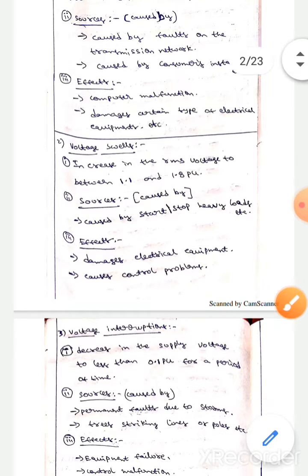The next one is voltage swells. It is an increase in the RMS voltage to between 1.1 and 1.8 pu. It is usually caused by starting or stopping heavy loads. The effects due to voltage swells are damage of electrical equipment and control problems. The next one is voltage interruptions. It is a decrease in the supply voltage to 0.1 pu.